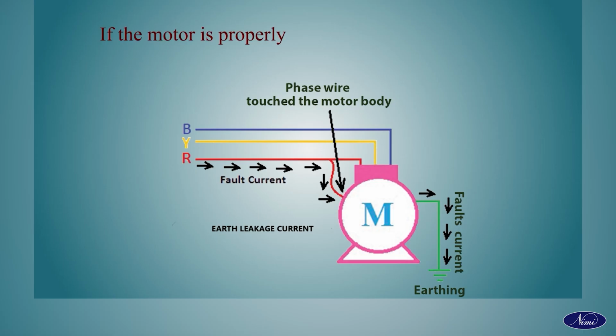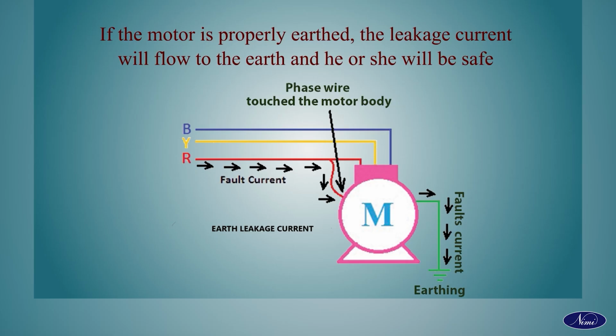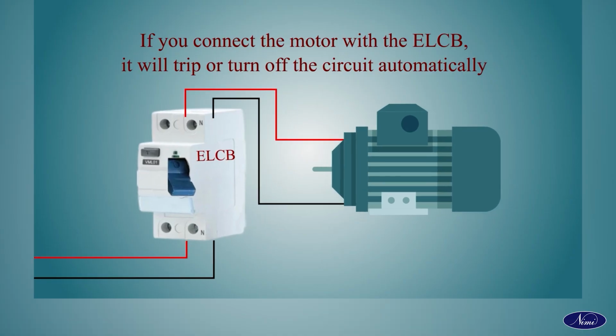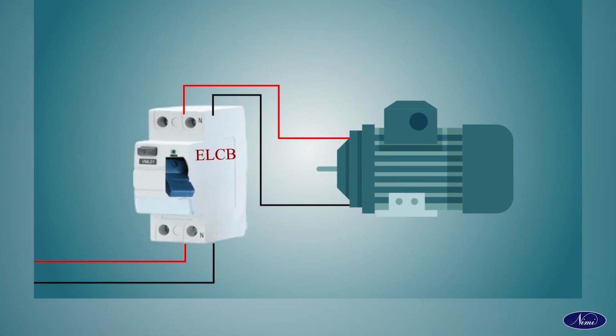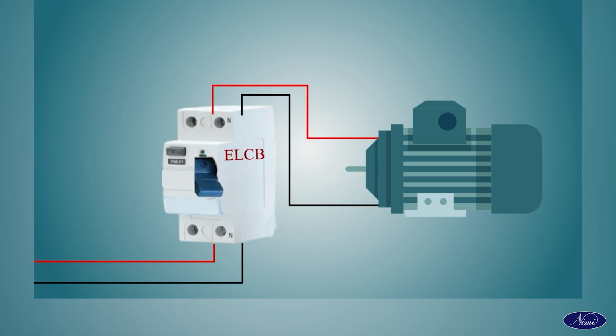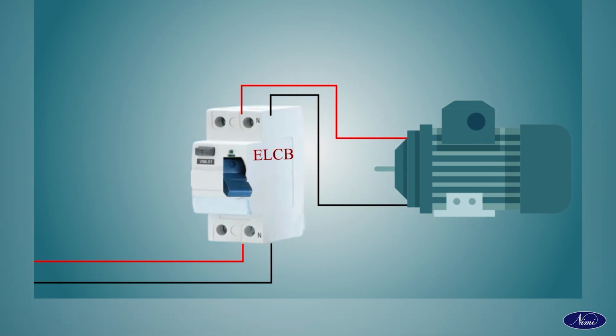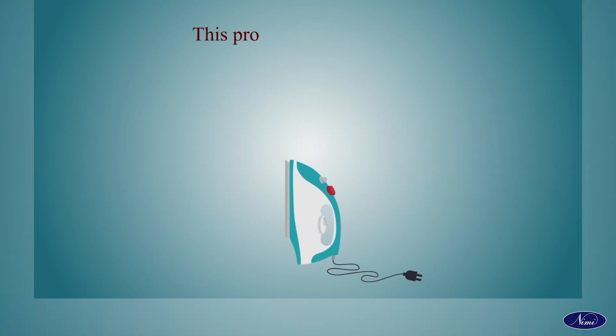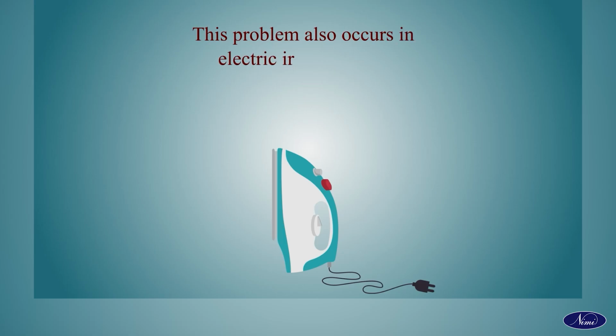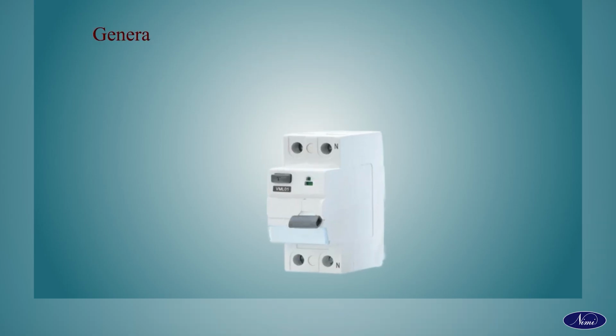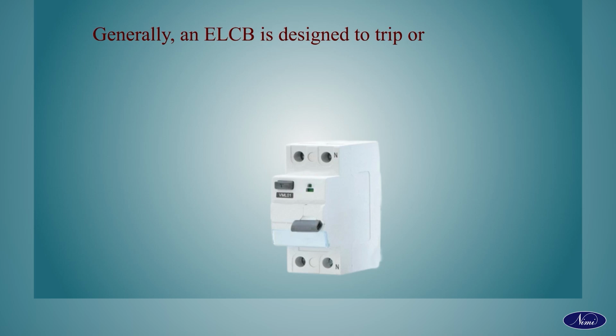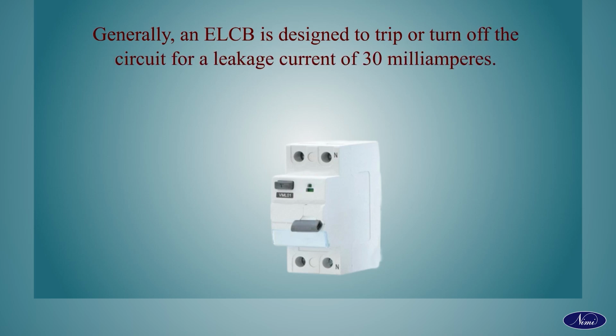If the motor is properly earthed, the leakage current will flow to the earth and he or she will be safe. If you connect the motor with the ELCB, it will trip or turn off the circuit automatically unless you rectify the insulation failure in the motor or replace the motor with a good one. This problem also occurs in electric irons usually. Generally, an ELCB is designed to trip or turn off the circuit for a leakage current of 30 milliamperes.